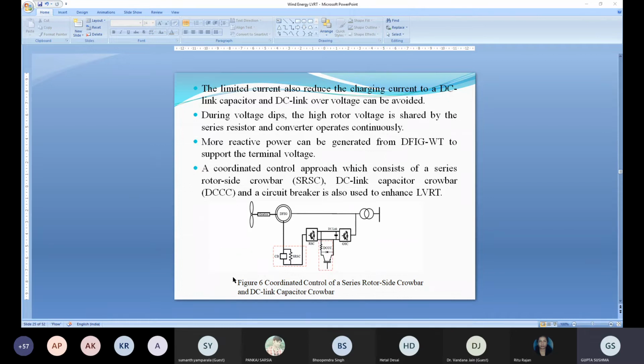Whatever energy exchange is happening is between the rotor and RSC. And this switch is also open during normal operation. But when there is a fault, an overcurrent, this circuit breaker will open and this resistor will come into the picture.